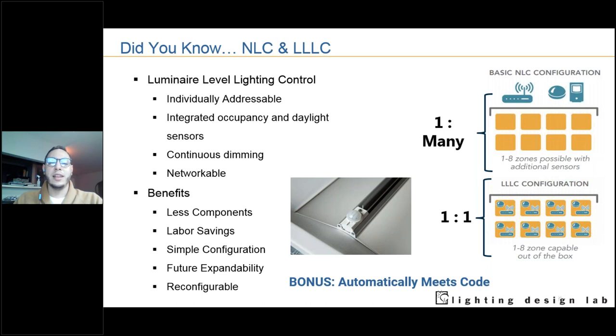A good way that we like to refer to these is the one-to-many and one-to-one motifs. For example, if you don't have luminaire level lighting controls in a space, you'll typically have one occupancy sensor and one daylight sensor for many fixtures being controlled. If you have luminaire level lighting controls, you will have one daylight sensor and one occupancy sensor per one fixture. So it's a good way for us to remember those.